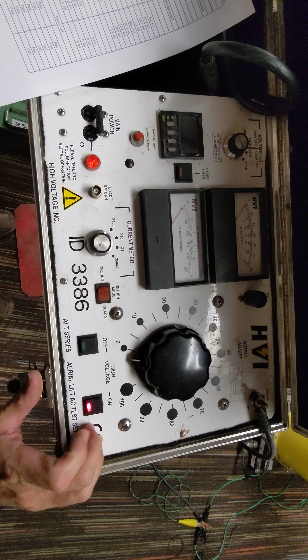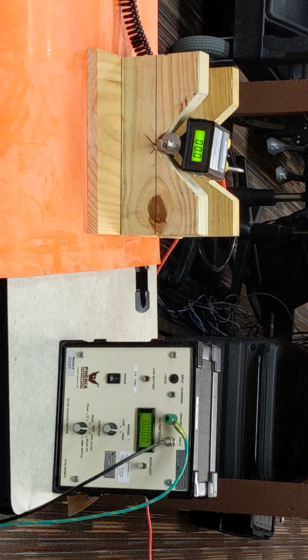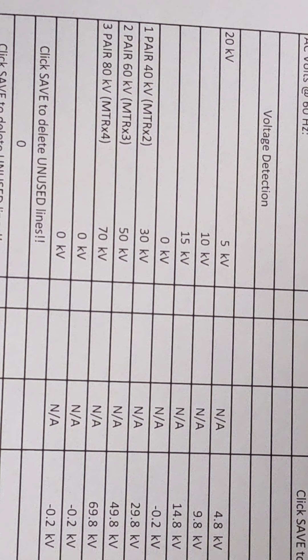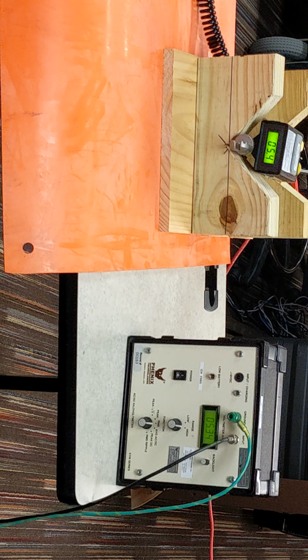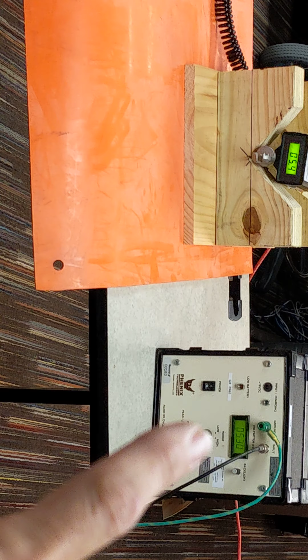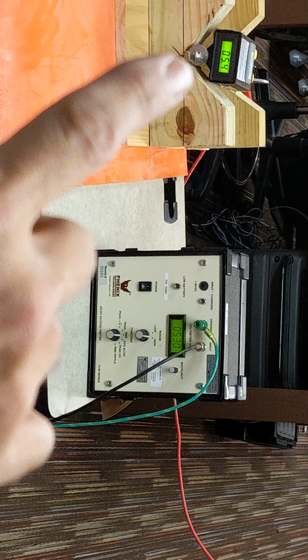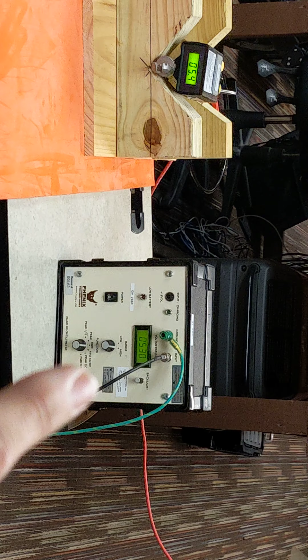So, because once again we're relying upon the display of the high voltage divider to tell us how much voltage is coming from the transformer, we won't even need to pay attention to our voltmeter to tell us how much voltage we're outputting. We're going to go directly off the display of our KVM 200. So, I'll go ahead and turn our console on. Go ahead and turn our high voltage circuit on, and we'll pay direct attention to the console of the high voltage divider. So I'm going to apply voltage, and as I apply voltage, you'll see the voltage increasing. And I'm going to go to our first data point, which is, sorry about that, 5 kV. 5 kV with a low of 4.8 and a high of 5.2.